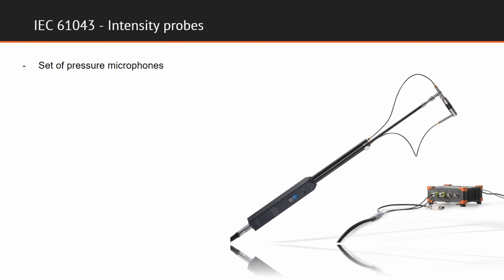of calibrations. Sound intensity is generally measured with sets of pressure sensing microphones. A set consists of two microphones with phase characteristics which are essentially equal, so they need to be as closely phase matched as possible. A very close match is necessary as even a small phase response difference may cause significant errors of the measured intensity. Consequently, sound intensity probe calibration is very important for having accurate and true results. And the calibration consists of sensitivity and phase check.